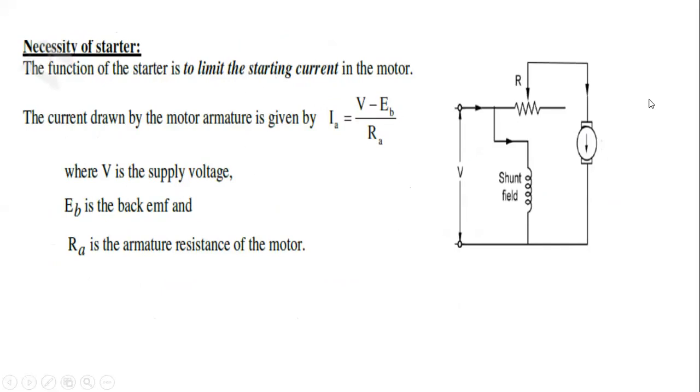When the motor draws high currents in the starting condition, more amount of heat will be dissipated and then the windings are damaged. Due to usage of the starter, we overcome this type of disadvantage. That is the main usage of a starter.